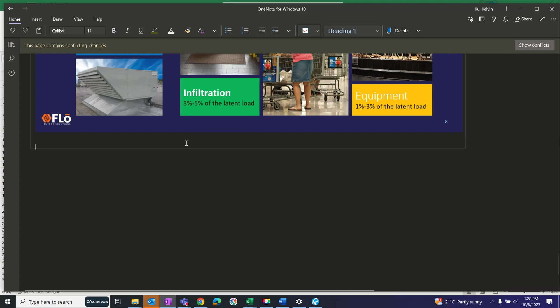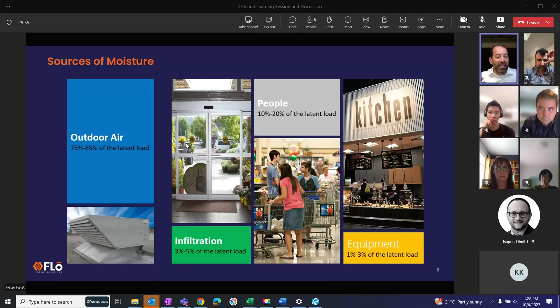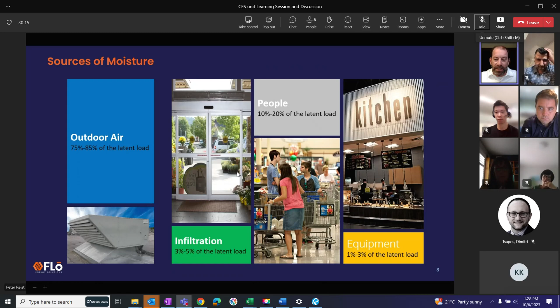Now, I think I also heard refrigeration is actually a dehumidifier. A refrigeration case will generally remove moisture from the air, but we don't want it to do that - how does it do it? It freezes that water on its coils, and that's not a good thing. So refrigeration equipment plays a role, but it's not creating moisture - it's potentially removing it if we don't do our jobs properly. Does that make sense? Yes, it does.